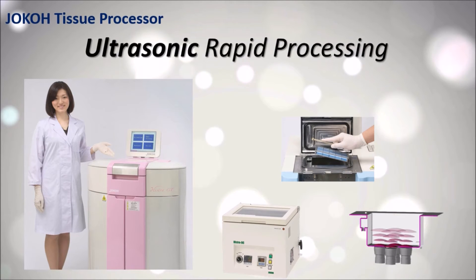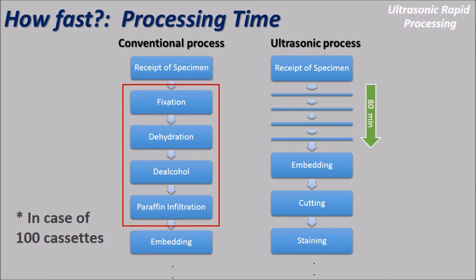Joko Tissue Processor uses a special rapid processing method called Ultrasonic. Ultrasonic enables rapid processing without damaging samples. By conventional method, the processing takes a long time. By Joko Histora series, the processing time of 100 cassettes is only 80 minutes.